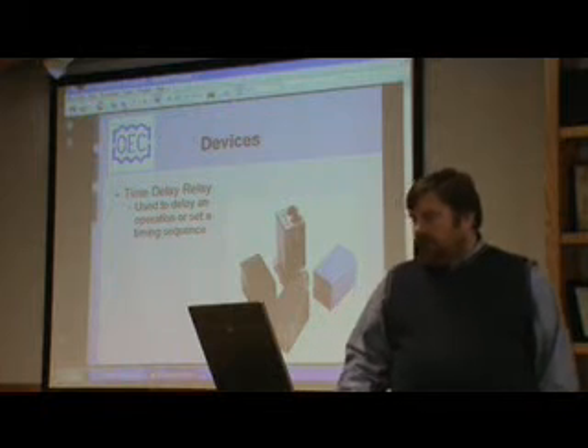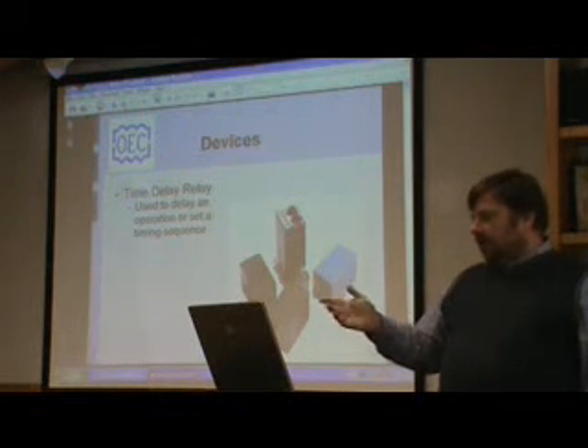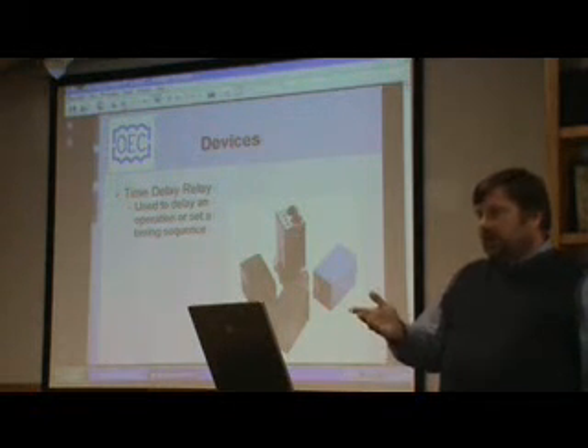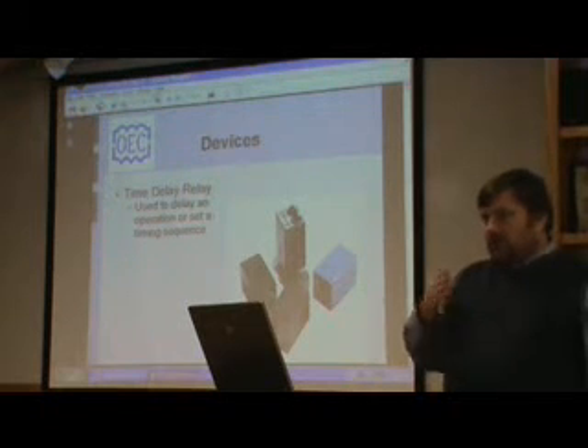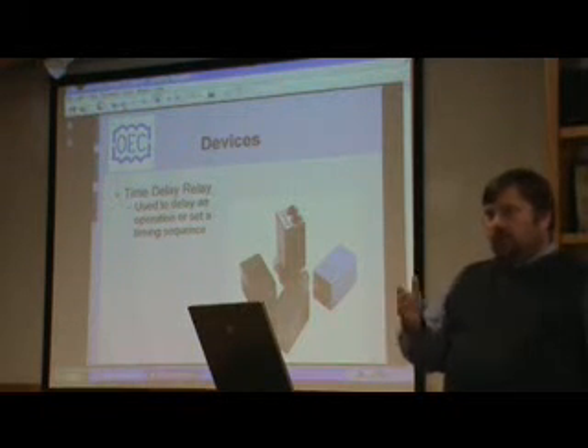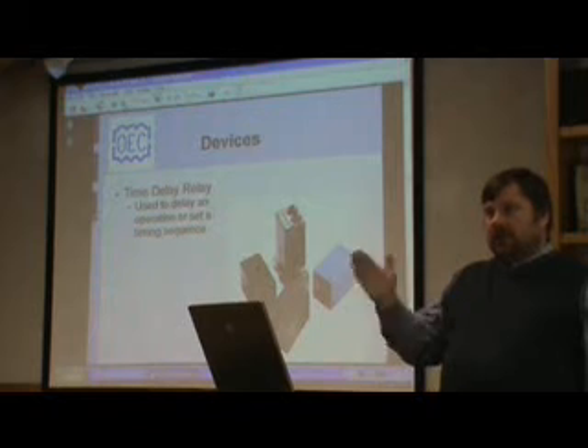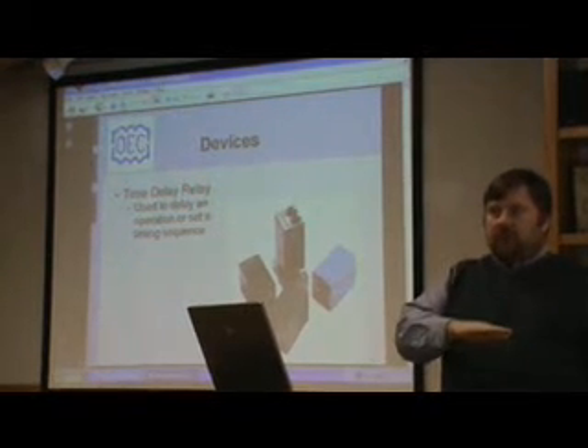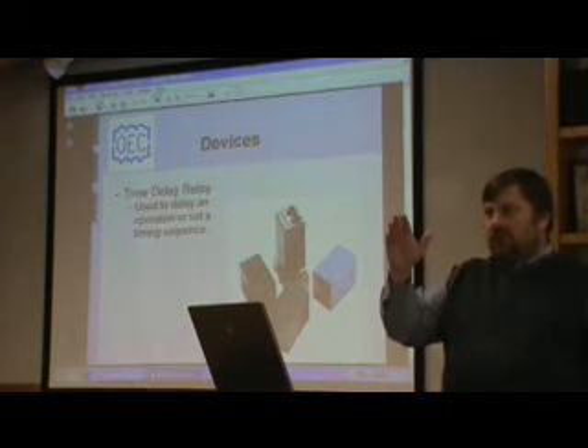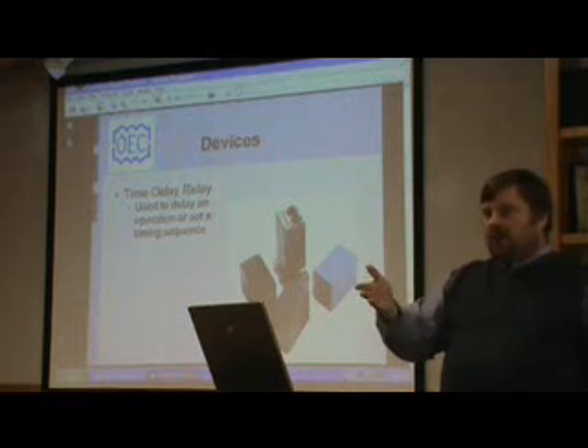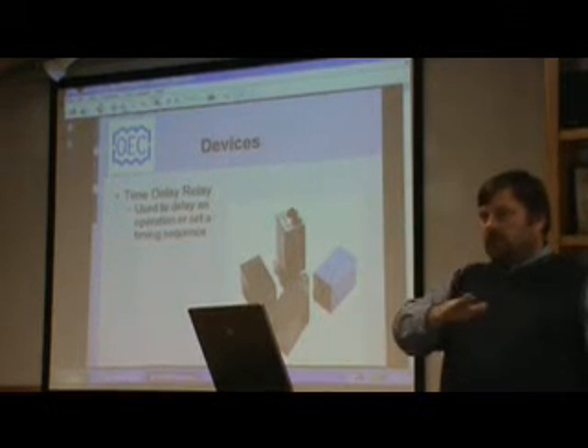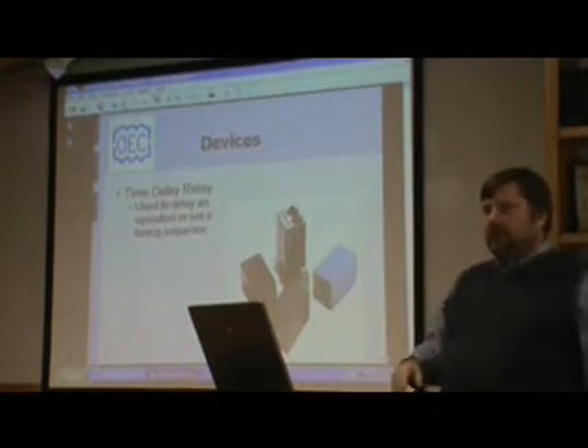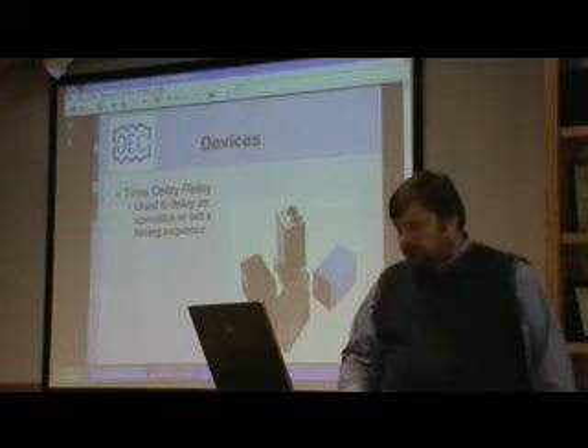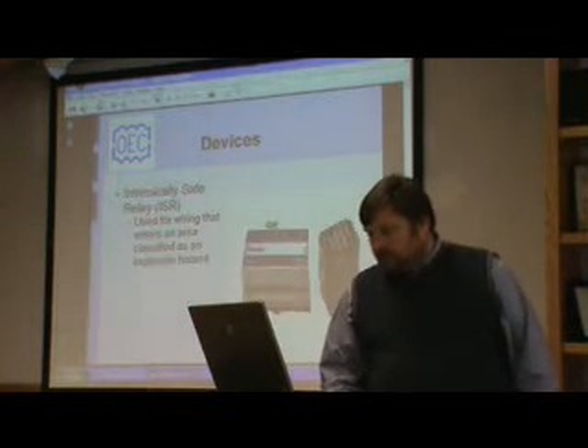that. And they come in various different types, on delays, off delays, different things we use. In some cases, if you have large motors and you don't want them both to start at the same time, we'll put a time delay in so that we delay that lag pump. So if the power goes off in the panel and the wet well starts to fill, when the power comes back on, if both pumps are called, one will start, delay a couple seconds, and the other will start, so you don't have a big power drain.